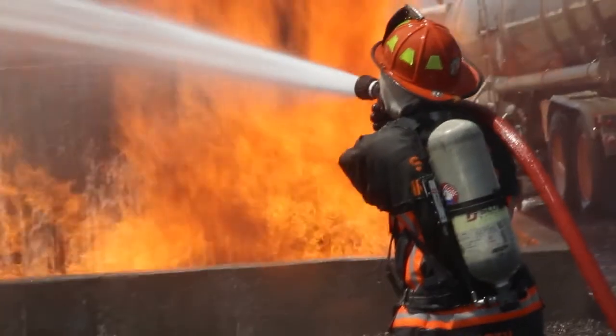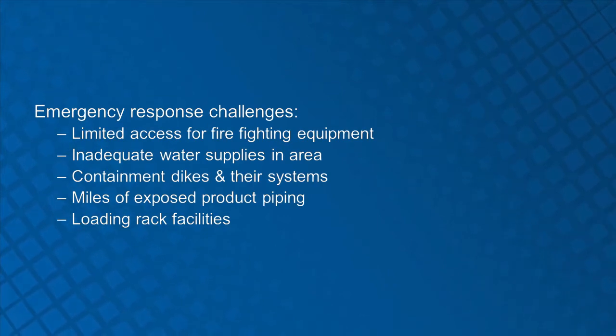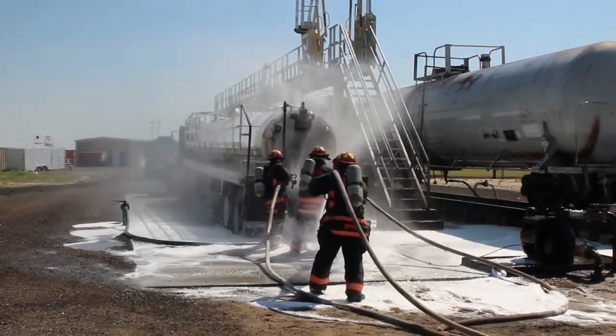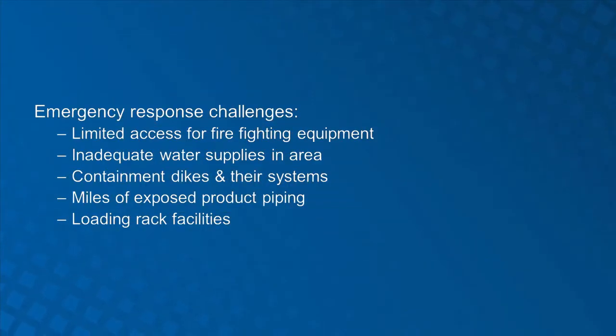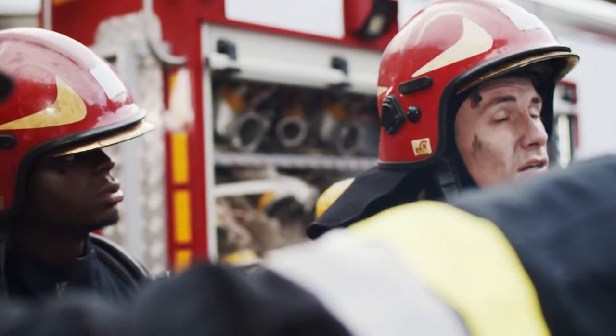There may be limited access both within the terminal itself and intake design for firefighting equipment. At times, some locations may have inadequate water supplies to fight any type of significant fire. Personnel may have to contend with containment dikes and their systems along with miles of exposed product piping. Liquid product terminals may also have loading racks subject to fire emergencies. Terminal operations can be very complicated and responding to a fire emergency can be very dangerous to personnel. It is also not unusual for terminals originally built in remote areas to now be surrounded by commercial and residential growth.